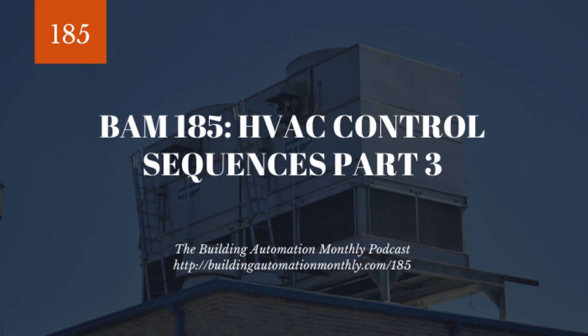Now, one of the things that folks will do is actually a trim and respond sequence. A trim and respond is where you're going to look at the average zone call for heating or call for air and/or damper position. And what will happen is you will either respond to that by increasing the discharge air pressure set point, or you will trim that by reducing the discharge air pressure set point. And this control is fairly common in advanced ASHRAE sequences.